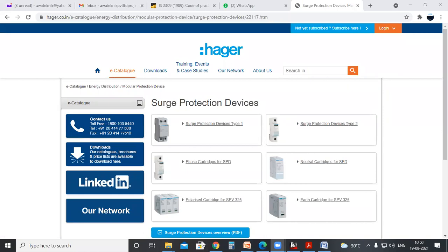Yeah, for the transformer, that is a separate one. For the transformer, that is a separate one to protect the transformer alone. Okay, that one is only for the transformer alone. This one I was saying about the total building. So we will be providing lightning arrestor protection, and lightning protection will be there for the transformer also, and the surge protection also will be there. The methods will be different. The connecting devices and the physical appearance will be different for the transformer's surge protective devices.